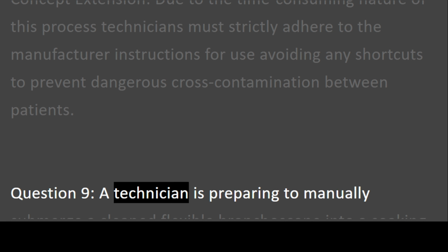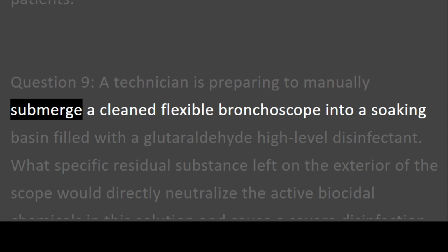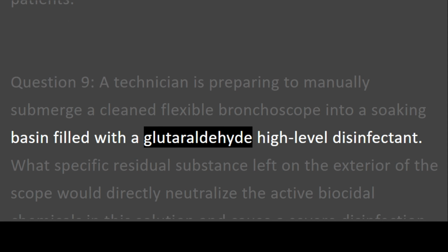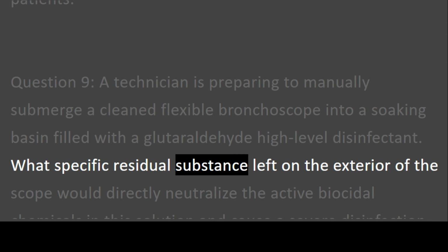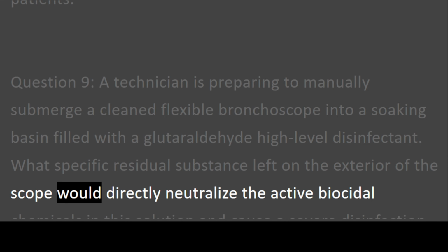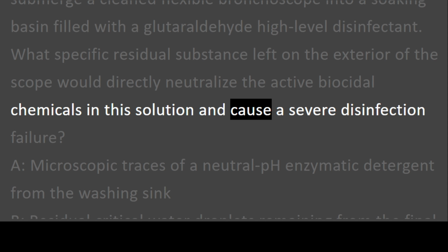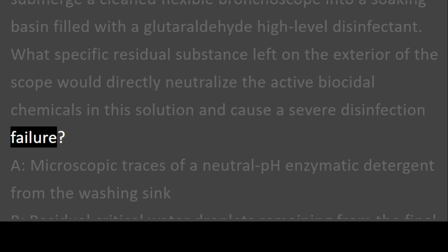Question 9. A technician is preparing to manually submerge a cleaned flexible bronchoscope into a soaking basin filled with a glutaraldehyde high-level disinfectant. What specific residual substance left on the exterior of the scope would directly neutralize the active biocidal chemicals in this solution and cause a severe disinfection failure?